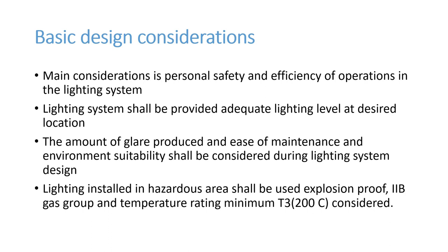Suppose we are designing lighting for an outdoor or plant area. In that area we need to consider whether it is a hazardous or non-hazardous area. If it is a hazardous area, you have to use explosion proof lamps. And for temperature, a minimum of 200 degrees, that is, T3 temperature rating lamps we need to select. So before calculating the lux level, you need to consider these 4 things.